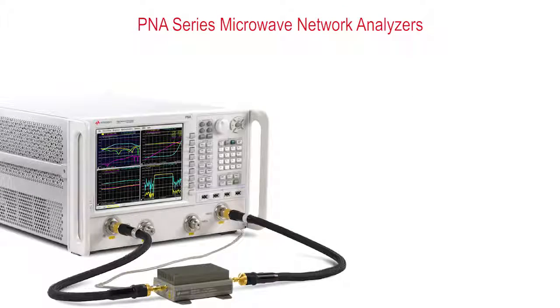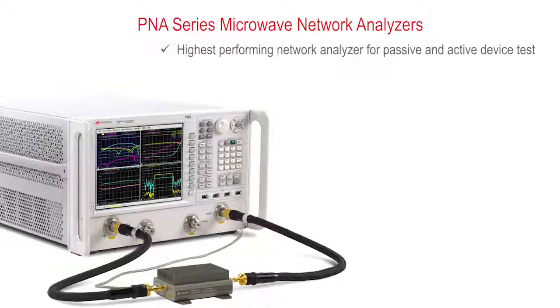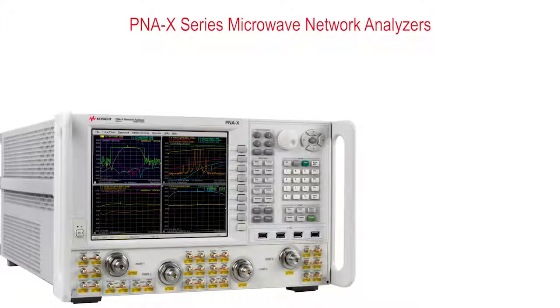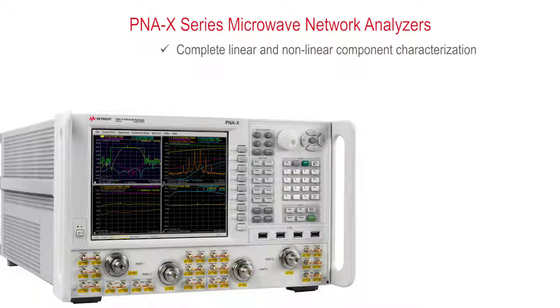For traditional S-parameter measurements, the PNA is simply the best. It is the highest performing microwave network analyzer in the industry for passive and active device tests, helping you create the most competitive products. You can choose from five frequency ranges up to 67 GHz and customize your PNA with just the right level of performance to meet your specific measurement and budget needs. The PNA-X provides complete linear and nonlinear component characterization in a single instrument.